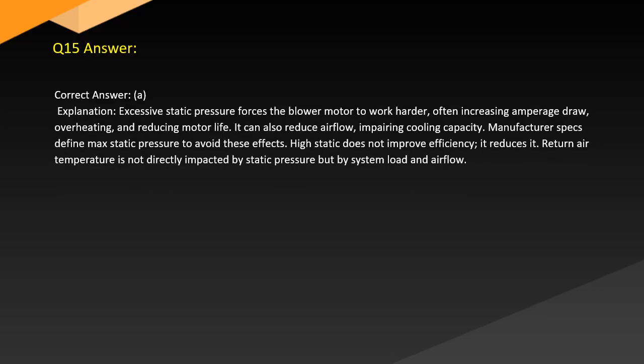Answer. Correct answer, A. Explanation. Excessive static pressure forces the blower motor to work harder, often increasing amperage draw, overheating, and reducing motor life. It can also reduce airflow, impairing cooling capacity. Manufacturer specs define max static pressure to avoid these effects. High static does not improve efficiency, it reduces it. Return air temperature is not directly impacted by static pressure but by system load and airflow.